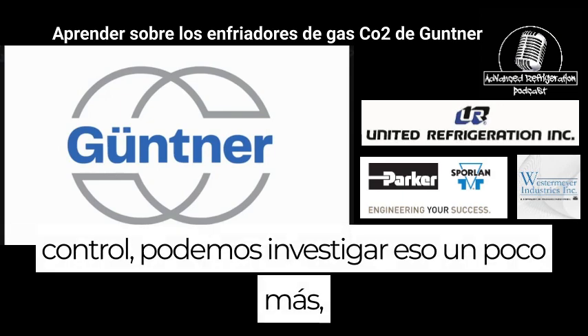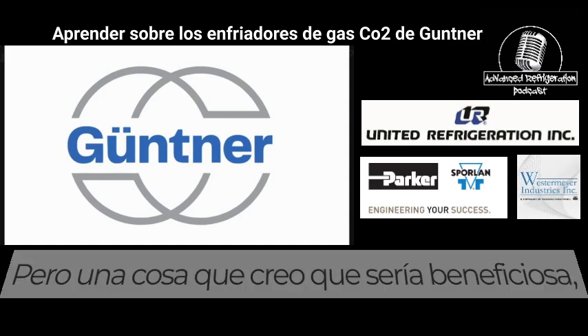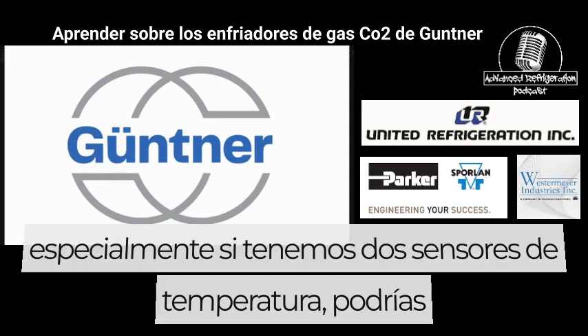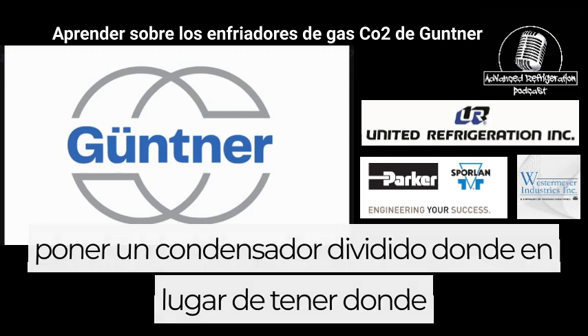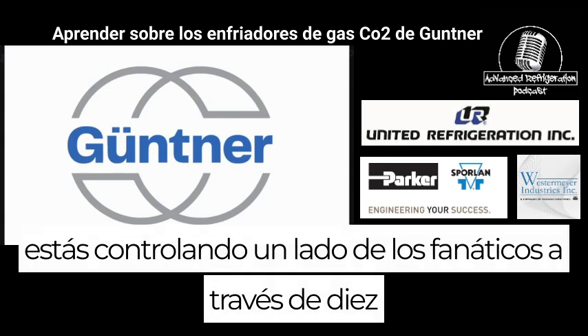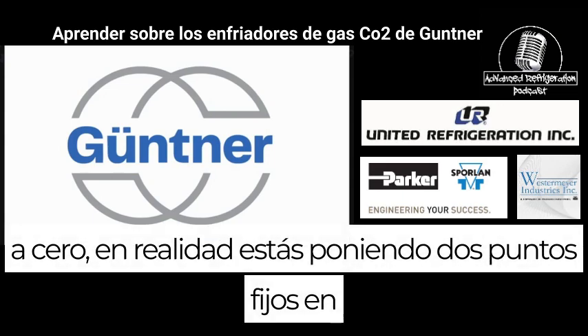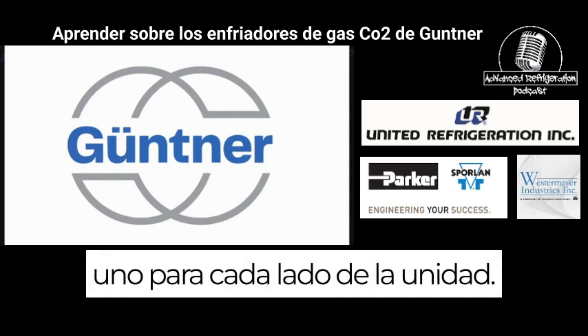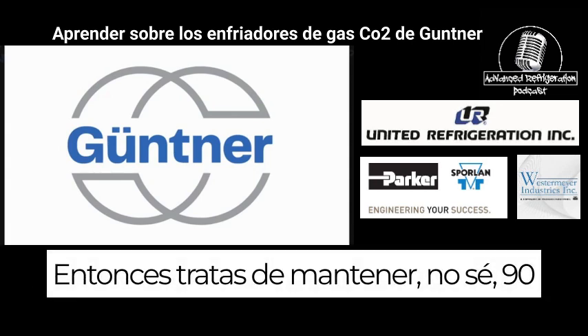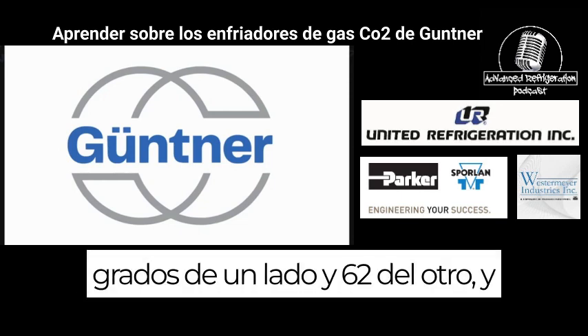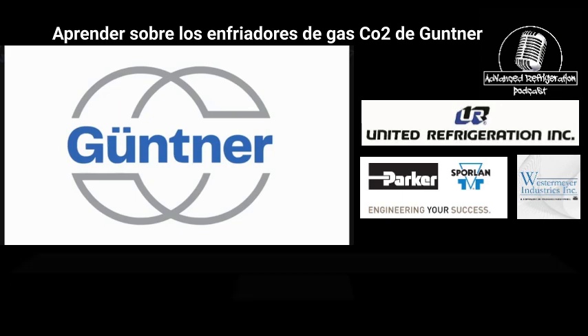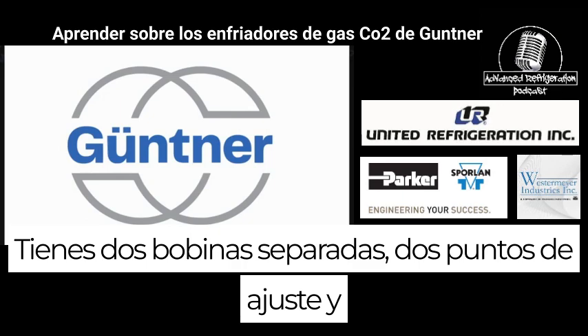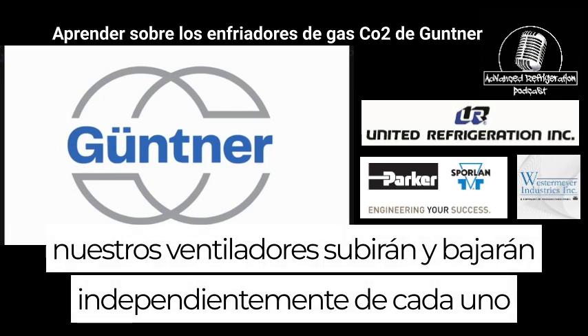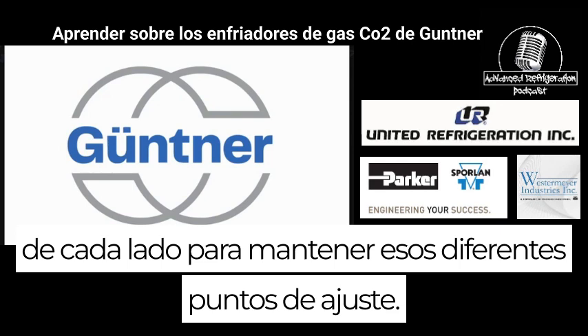We can look into that a little bit more, see if that would be what you're asking. But one thing I think would be beneficial, especially if we have two temperature sensors, you could do a split condenser where, instead of controlling one side of the fans via 10 to zero, you're actually putting two set points in, one for each side of the unit. So you're trying to maintain, I don't know, 90 degrees on one side and 62 on another, and our unit is capable of doing that. You're having two coils, two set points, and our fans will ramp up and down independently of each side to maintain those different set points.